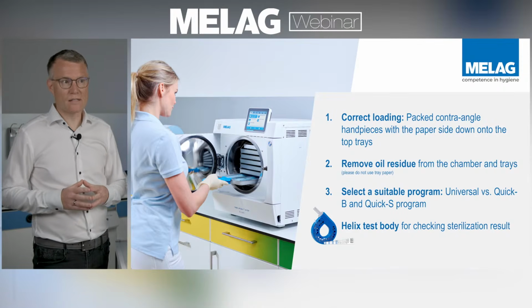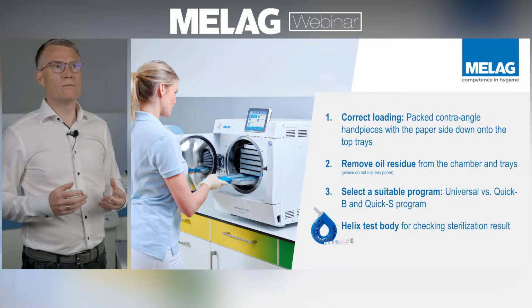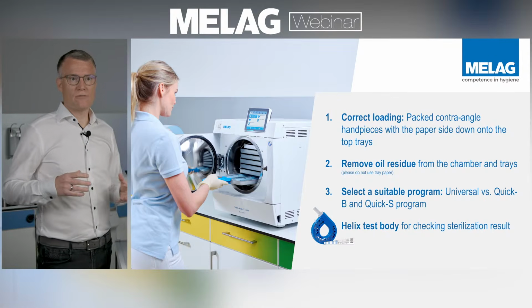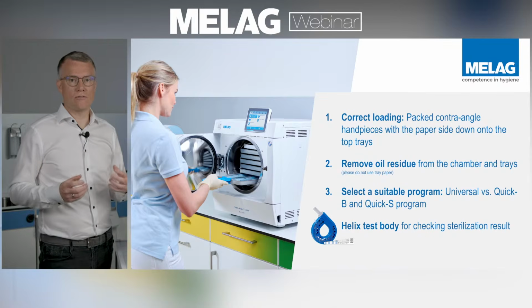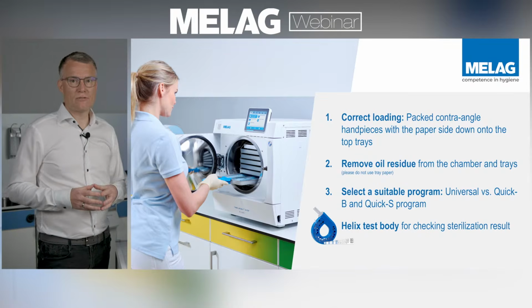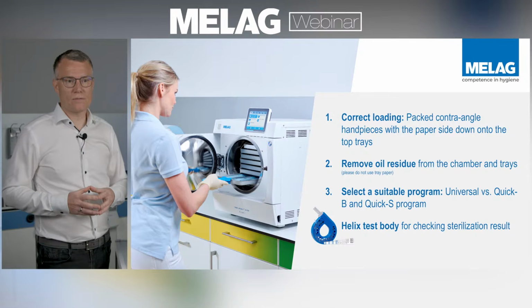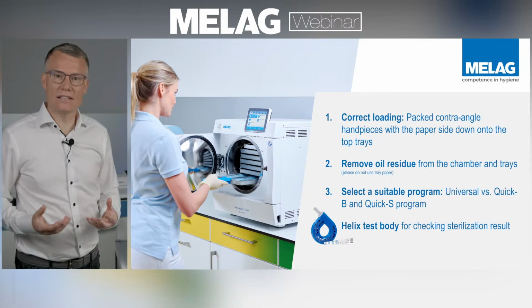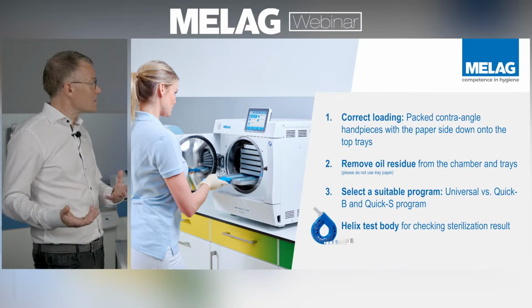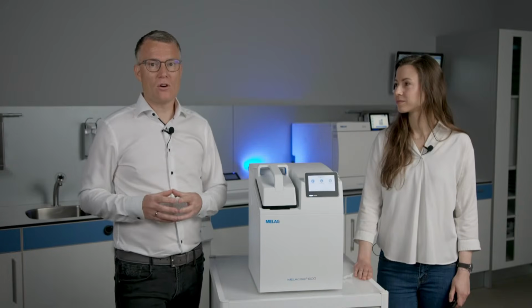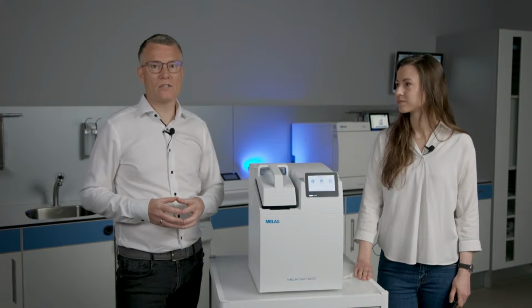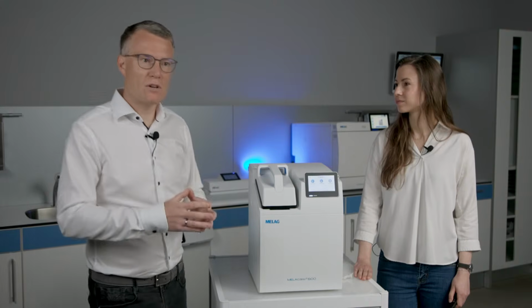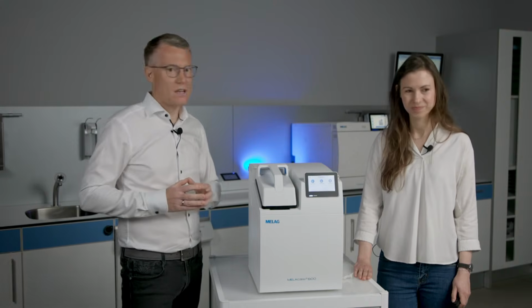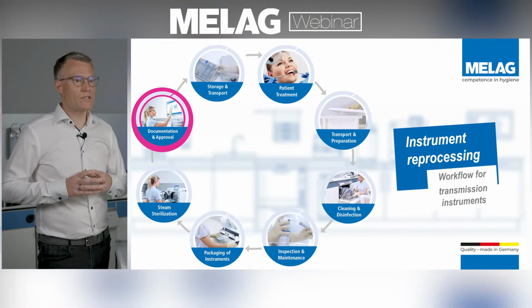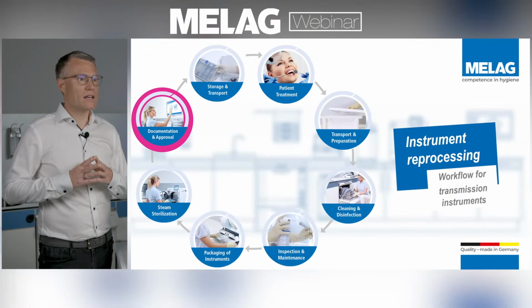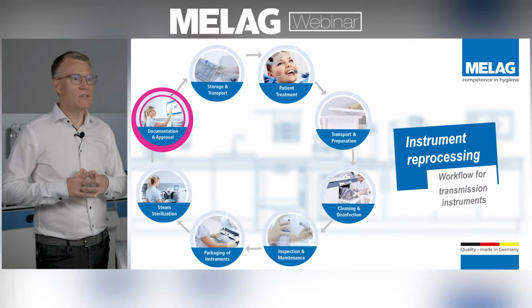Right, and last but not least, it's more and more common, also in an international context, to have an external control of the sterilization parameters. So it's more and more common to use an indicator, the so-called helix test, for example, that is checking all the parameters, including the vacuum, so that you can really be sure that your sterilizer is doing a good job at the end. Next step in the reprocessing cycle would be the documentation and approval.